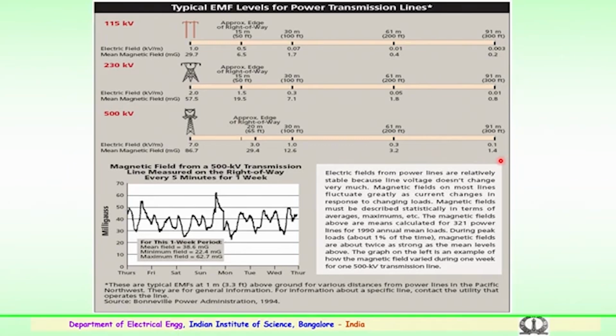Because of this, the magnetic fields should be of concern and must be described statistically, in terms of averages or maximum or minimum values, since the fluctuation depends upon the load. The magnetic fields above the mean are normally calculated for various transmission lines, and they can be monitored and measured. Various values for the different transmission systems are given here.